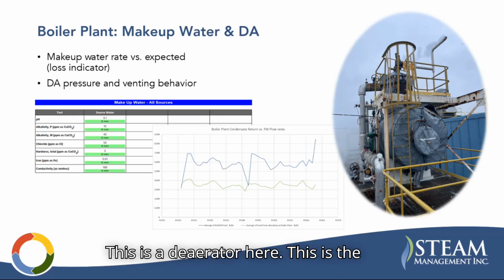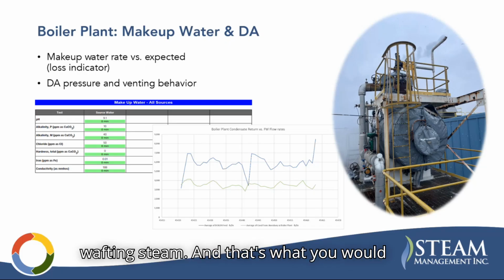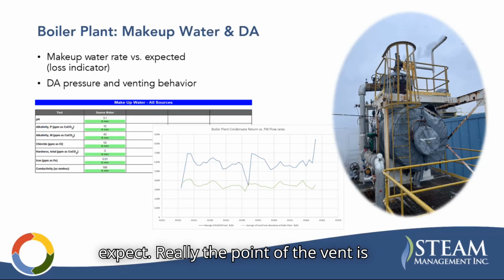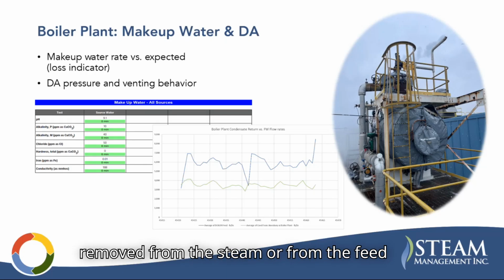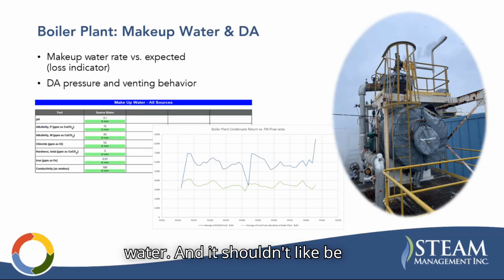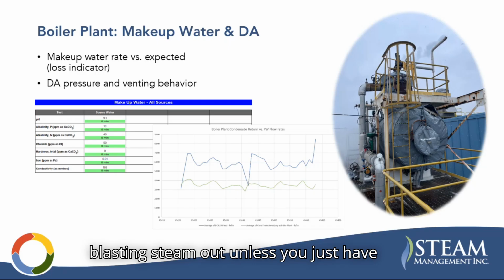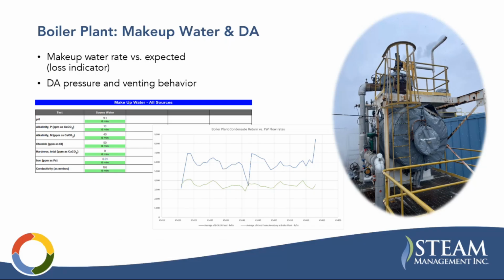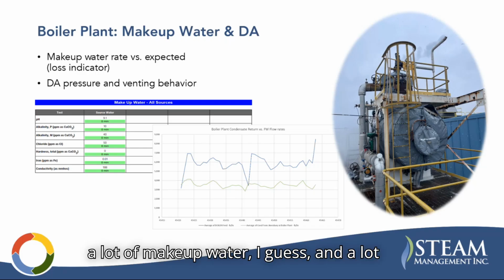This is a deaerator here. This is the vent, and this is a well-performing deaerator. The vent is just wafting steam, and that's what you would expect. Really, the point of the vent is to reject the air that's being removed from the feed water, and it shouldn't be blasting steam out unless you just have a lot of makeup water, I guess, and a lot of air to remove.